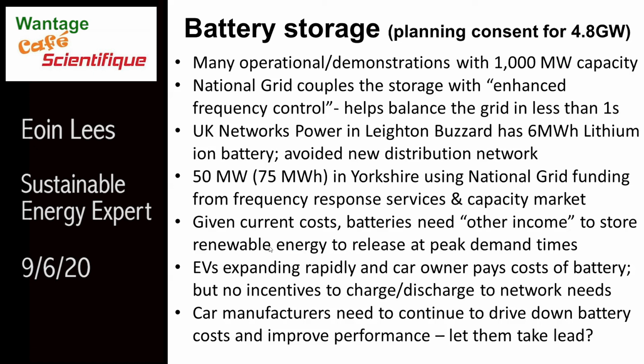Now this is important to know. Basically, that's one of the ways they control the grid, helping balance it in less than a second - they can change the frequency. It's normally 50 cycles a second, the AC that comes into our homes, but they have the power to change that between 49.5 and 50.5, as long as they get it right over the day. And so they use that storage because batteries are very fast - a great chance to use enhanced frequency control.